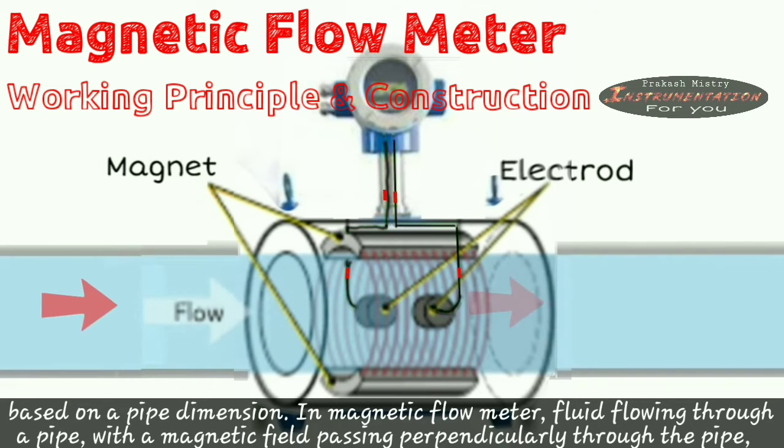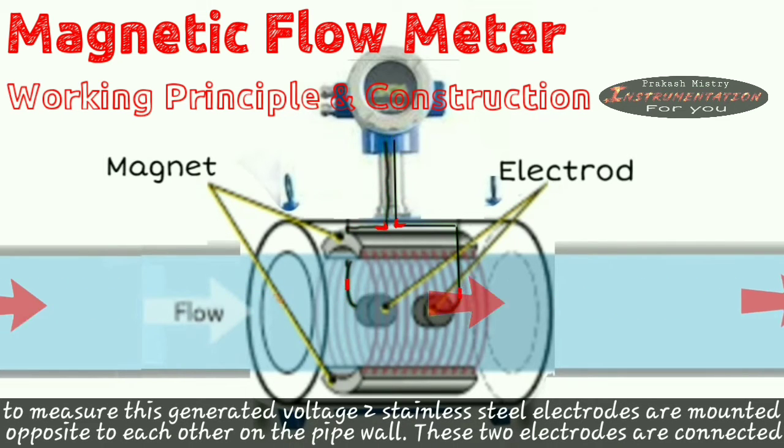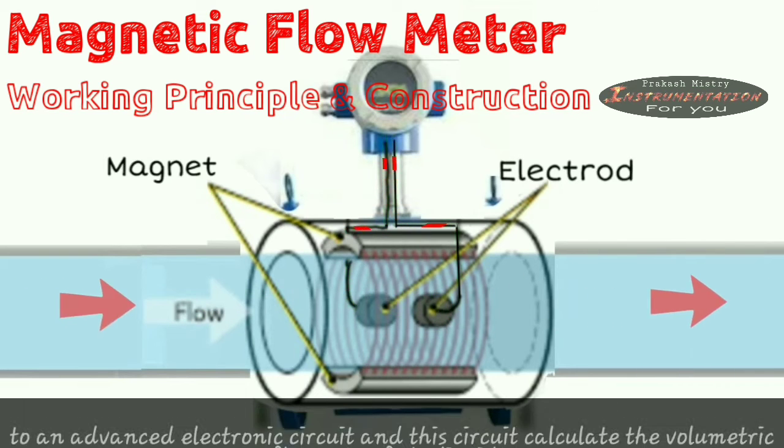In a magnetic flow meter, fluid flowing through a pipe with a magnetic field passing perpendicularly through this pipe. Here the liquid flowing through the pipe acts as a conductor and this induces a voltage which is proportional to the average flow velocity. To measure this generated voltage, two stainless steel electrodes are mounted opposite to each other on the pipe wall. These two electrodes are connected to the advanced electronic circuit and this circuit calculates the volumetric flow rate of the liquid.